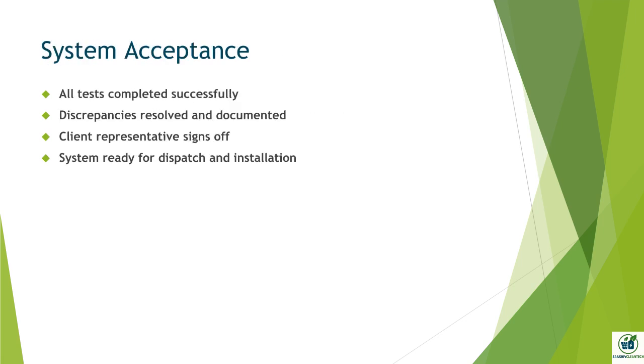Once all tests are completed and any discrepancies resolved, the system is formally accepted by the client. This includes signed documentation and test records. Acceptance confirms that the BESS is ready for dispatch and installation. It's a moment of assurance for the vendor, the client, and the future performance of the system.